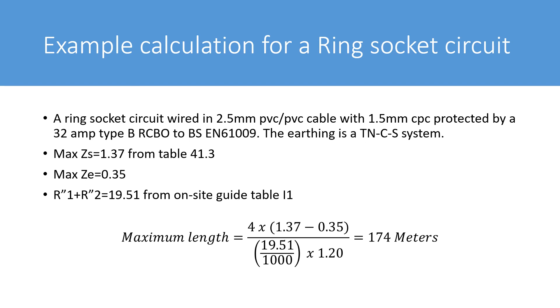Now 174 meters seems very long and it's much longer than it would be in practice and if you do the volt drop equation I think that you would find that the maximum length would be much less than that. So it's important to do the equations for both the impedance and the volt drop when calculating the length of the circuit.